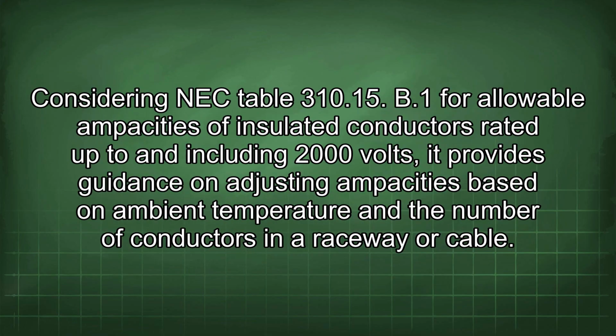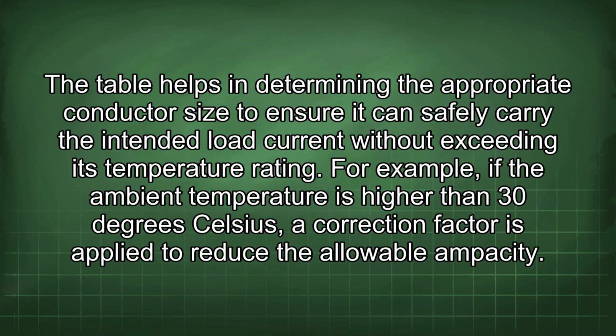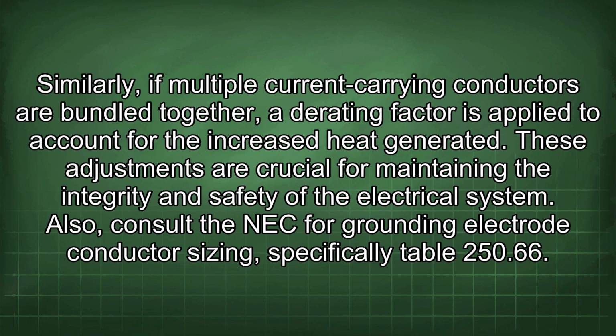Considering NEC Table 310.15(B)(1) for allowable ampacities of insulated conductors rated up to and including 2000 volts, it provides guidance on adjusting ampacities based on ambient temperature and the number of conductors in a raceway or cable. The table helps in determining the appropriate conductor size to ensure it can safely carry the intended load current without exceeding its temperature rating. For example, if the ambient temperature is higher than 30 degrees Celsius, a correction factor is applied to reduce the allowable ampacity. Similarly, if multiple current-carrying conductors are bundled together, a derating factor is applied to account for the increased heat generated. These adjustments are crucial for maintaining the integrity and safety of the electrical system.